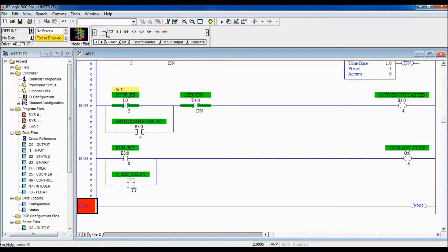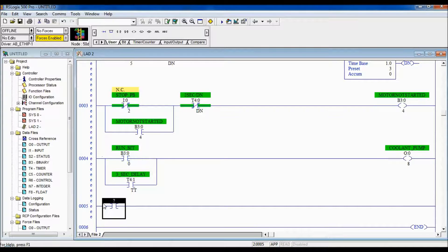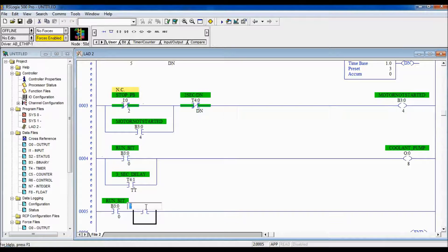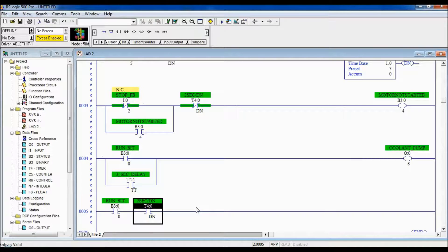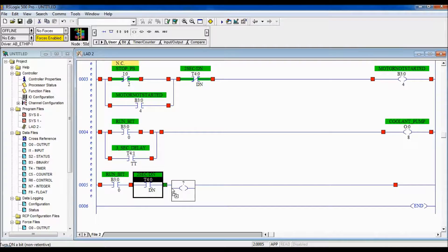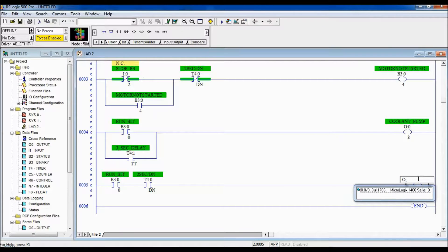The other output is the cutting motor. The motor should only be on if the run bit is true AND the 2-second delay timer is done — T4:0/DN. As soon as stop is pressed, the run bit goes false, which immediately cuts power to the motor output. So the motor cannot be on if the run bit is false. The cutting motor output is located at O:0/9.